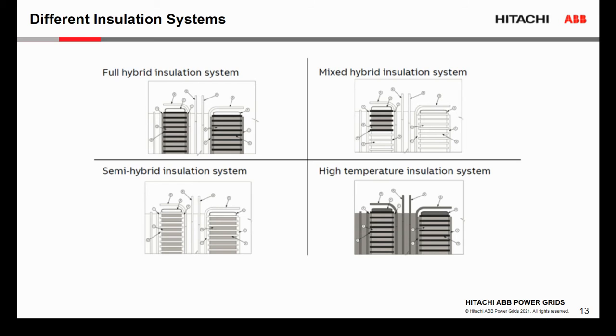And then another example of different insulation system is the semi-hybrid system. So in this case, we use only high temperature insulation tape on the conductor. And then in the high temperature insulation system where the permissible hotspot temperature is 155 degrees C, we have solid insulation like paper and spacers and winding insulation made of high temperature insulation, and also the transformer is filled with ester fluid. Because with ester fluid we can go to higher temperatures.